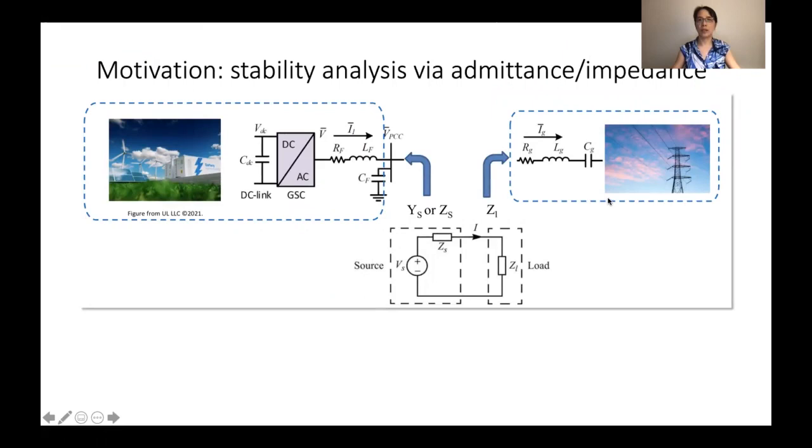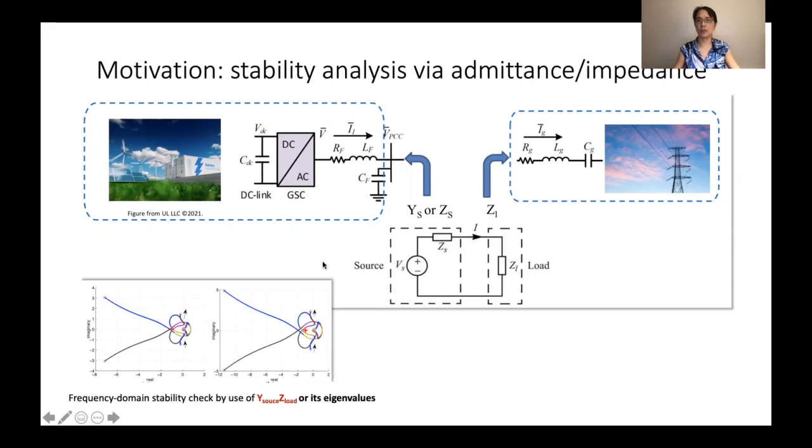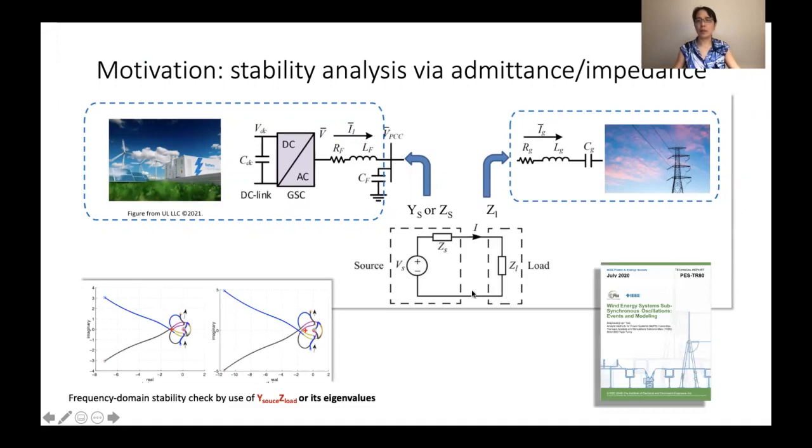First, why do we need admittance? For power grid, we usually like to do stability analysis and we can split a system through a bus and looking at the system from left and right as two components, and each can be impedance or admittance. With that, we have the frequency domain response. We can conduct stability analysis using Nyquist plot or Bode plot, these kind of criteria. And this method has been widely used in power grid industry.